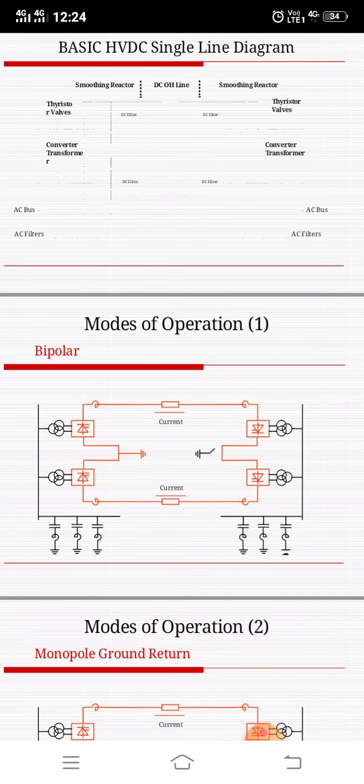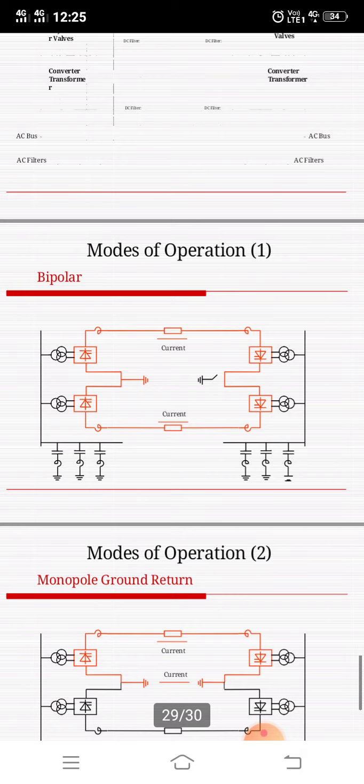The third type is bipolar without a dedicated return path for monopolar operation. This scheme, without electrodes or a dedicated metallic return path, gives the lowest initial cost. Monopolar operation is possible by means of bypass switches during a converter pole outage, but not during an HVDC conductor outage. A short bipolar outage will follow a converter pole outage before bypass operation can be established.